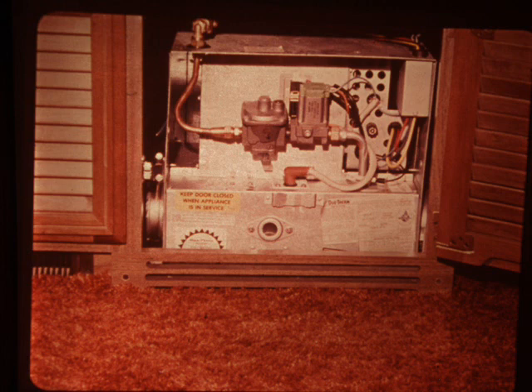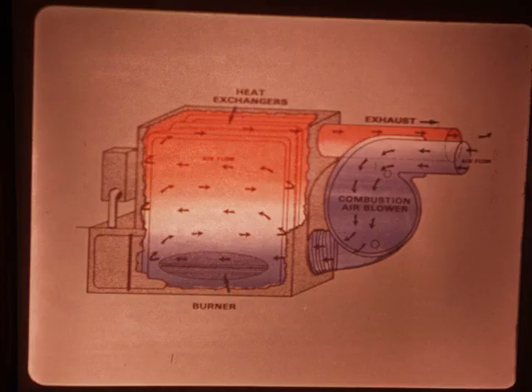It uses a solid-state direct spark ignition system. There is no pilot light, no air adjustment, and no manual lighting required. The furnace features a sealed combustion system. That is, air for combustion is drawn from outside the vehicle, then returned outside.